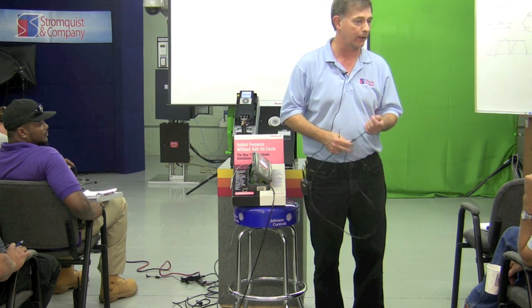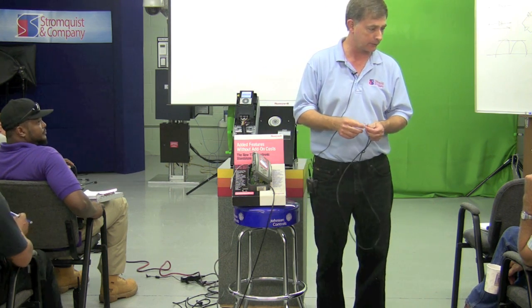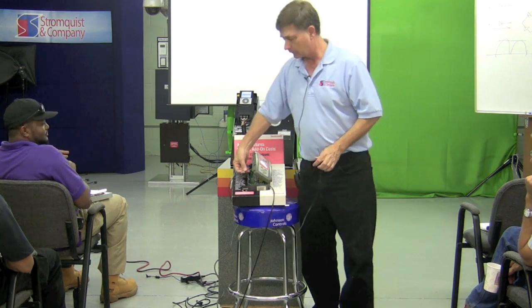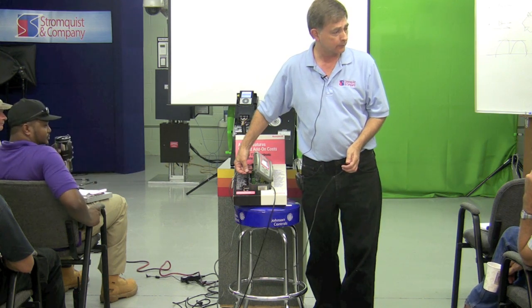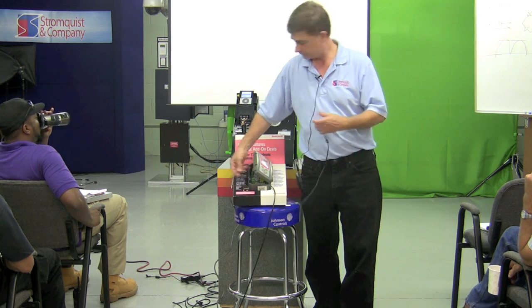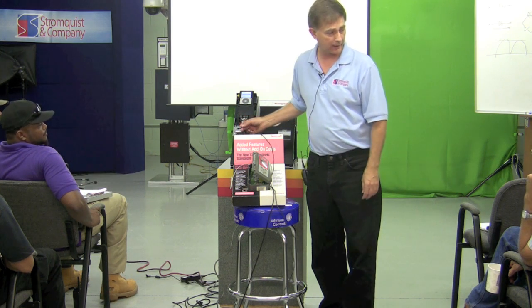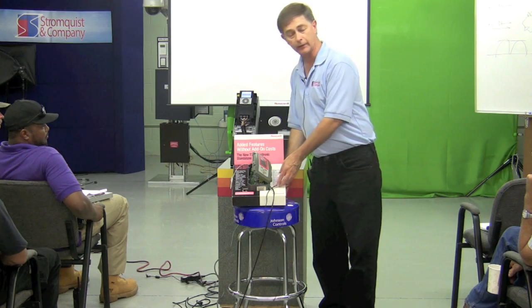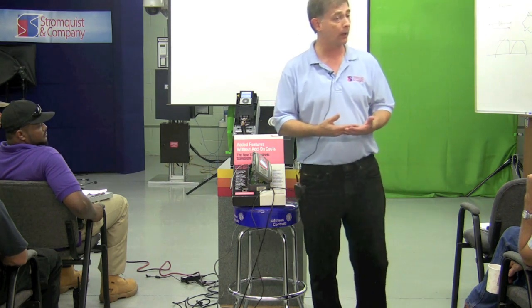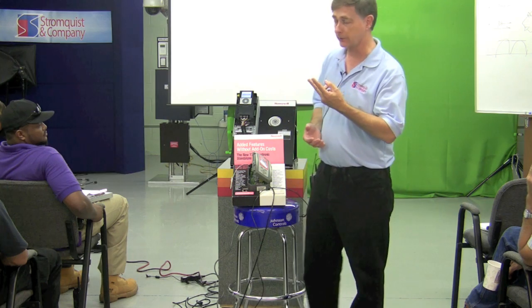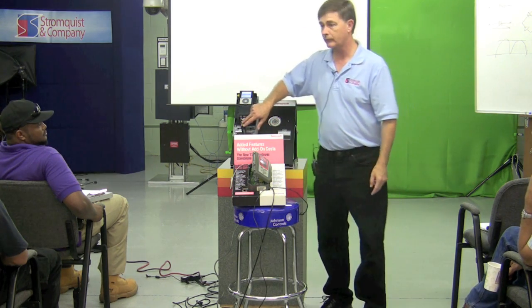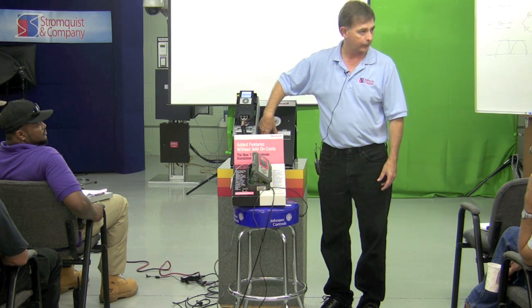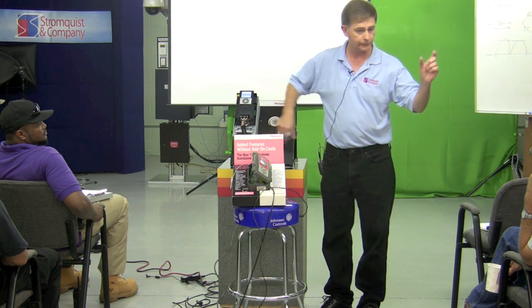All it takes is two conductors, shielded, hooked to your zero to ten volt DC output across terminals two and three for analog input one. For permission to run you need a switch or time clock with dry contacts across terminals six and eight. That's all we need.